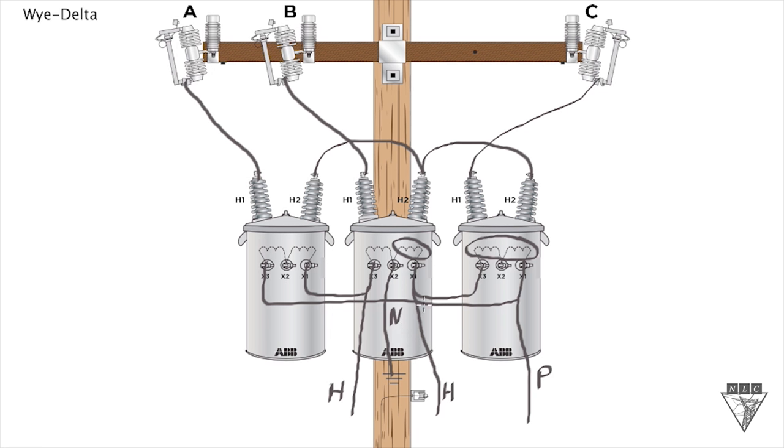One of the advantages of a system like this, a Y-delta, is you can use on the primary side it can be used in a three wire or four wire system. So like a delta or an ungrounded Y three wire system, or you can utilize it on a grounded Y system where you have four wires.